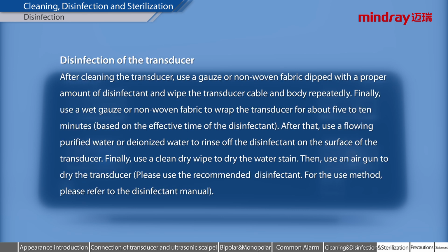Disinfection of the transducer. After cleaning the transducer, use a gauze or non-woven fabric dipped with the proper amount of disinfectant and wipe the transducer cable and body repeatedly. Finally, use a wet gauze or non-woven fabric to wrap the transducer for about 5 to 10 minutes, based on the effective time of the disinfectant. After that, use flowing purified water or deionized water to rinse off the disinfectant on the surface of the transducer. Finally, use a clean dry wipe to dry the water stain. Then, use an air gun to dry the transducer. Please use the recommended disinfectant. For the use method, please see the disinfectant manual.